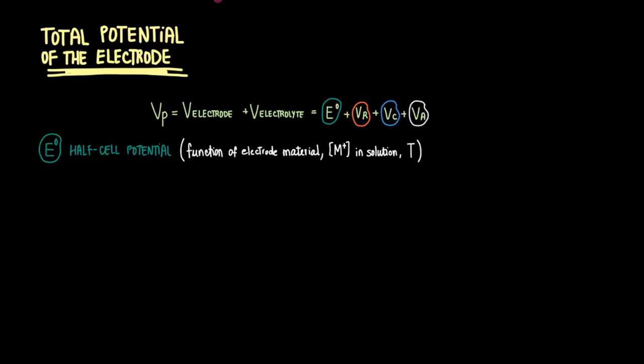The half cell potential is a function of the electrode material, the concentration of metal cations in solution in which the electrode is immersed, and the temperature. In principle, there is another half cell potential at the interface between any two surfaces. Also, for differential biopotential measurements between two identical electrodes, the half cell potentials cancel out, which is great. This half cell potential is also relative to the standard hydrogen electrode.